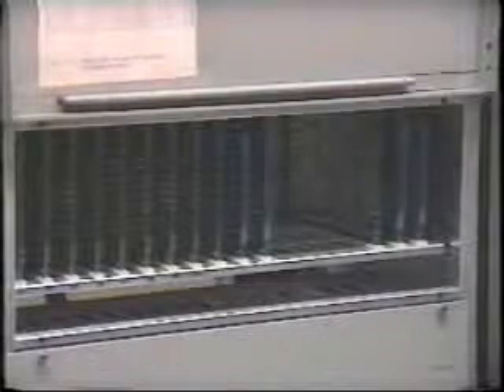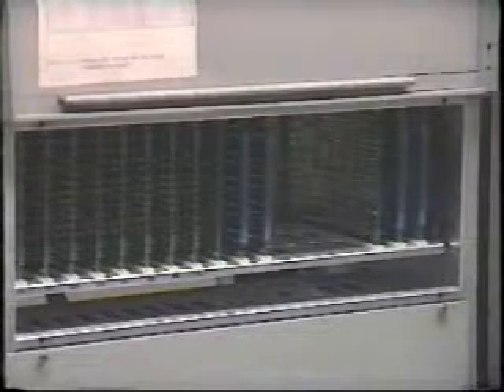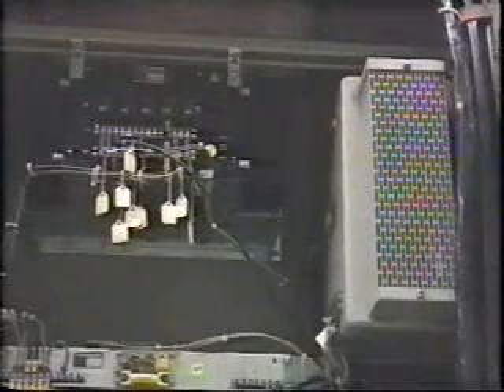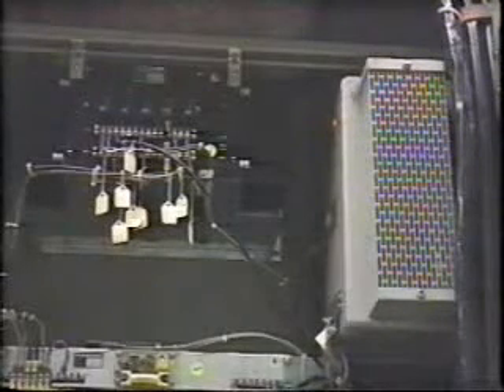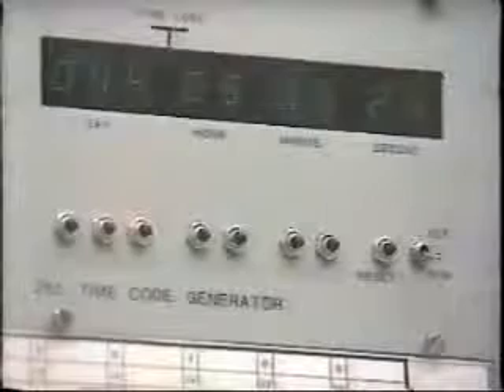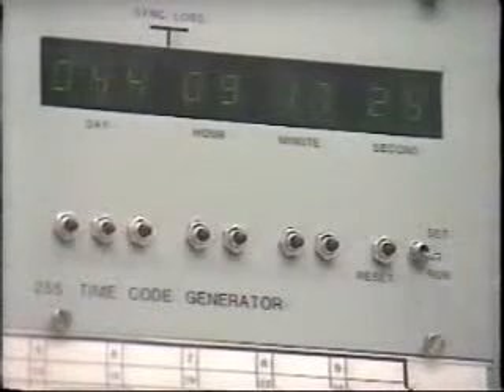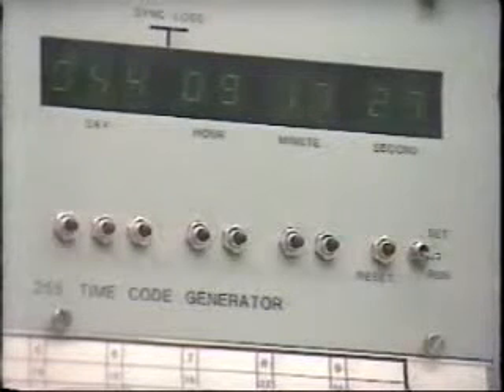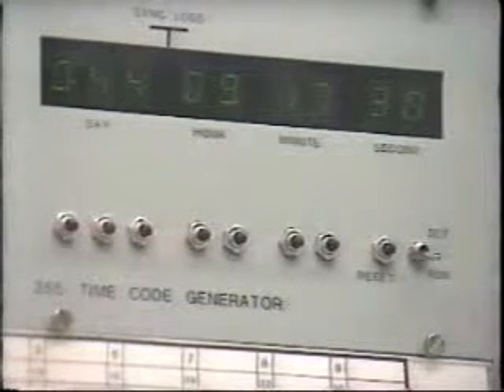Once the data is saved on magnetic tape, we can get a hard copy printout of the waveforms for analysis. In addition to the oscillograph machines themselves, there are several accessories that must be installed to complete the recording system. And these include starting sensors or triggers to start the recordings, signal conditioners to prepare the data for recording, power supplies and inverters to provide an uninterruptible power source for the oscillographs, and time clocks to keep track of the exact time of recording. The time log helps coordinate the output from many recorders.